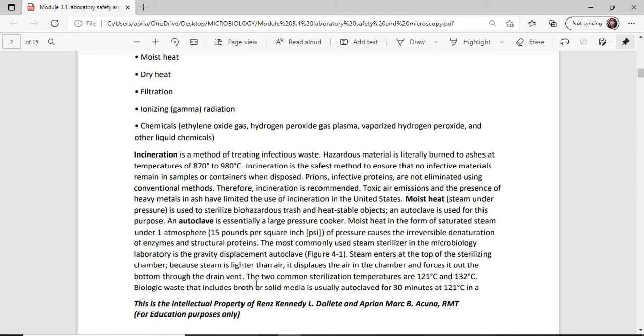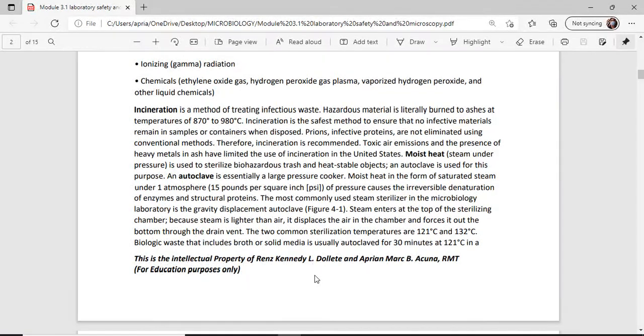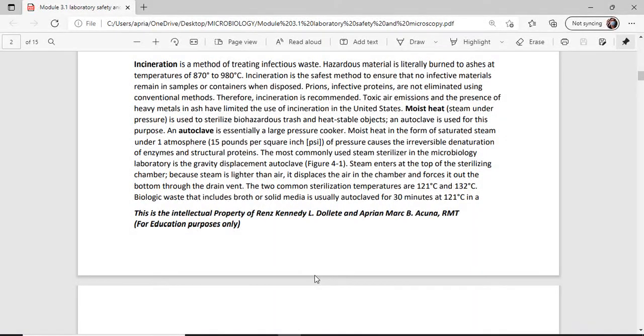In the gravity displacement sterilizer, sterilization temperatures are 121 degrees Celsius and 132 degrees Celsius. Biologic waste, including broth and solid media, is usually autoclaved for 30 minutes at 121 degrees Celsius. What does our broth look like for microbiology? Broth here is not the kind used for cooking. This broth is a culture media.